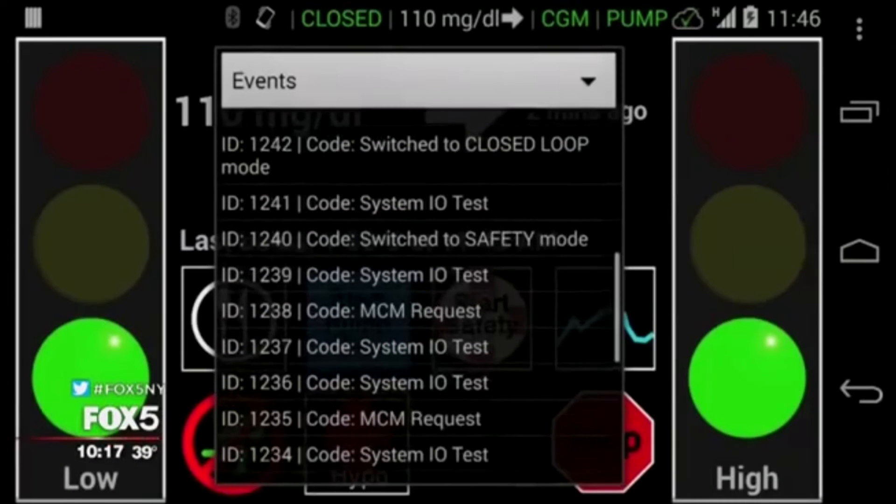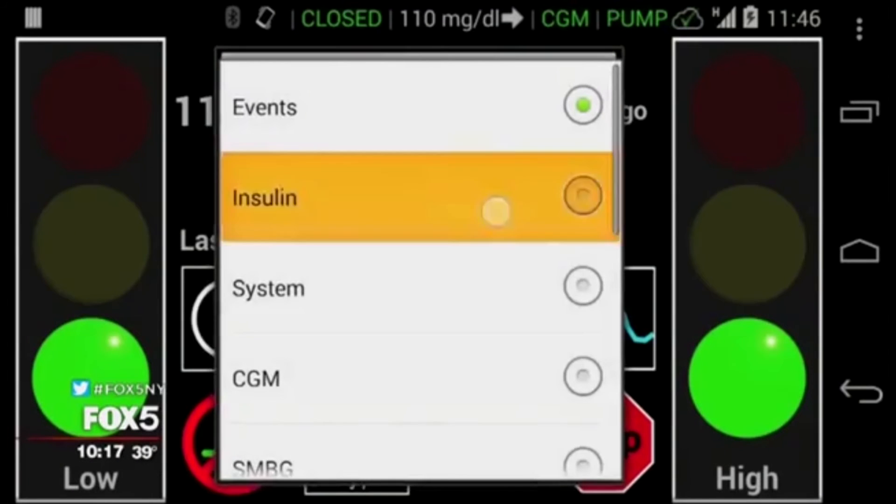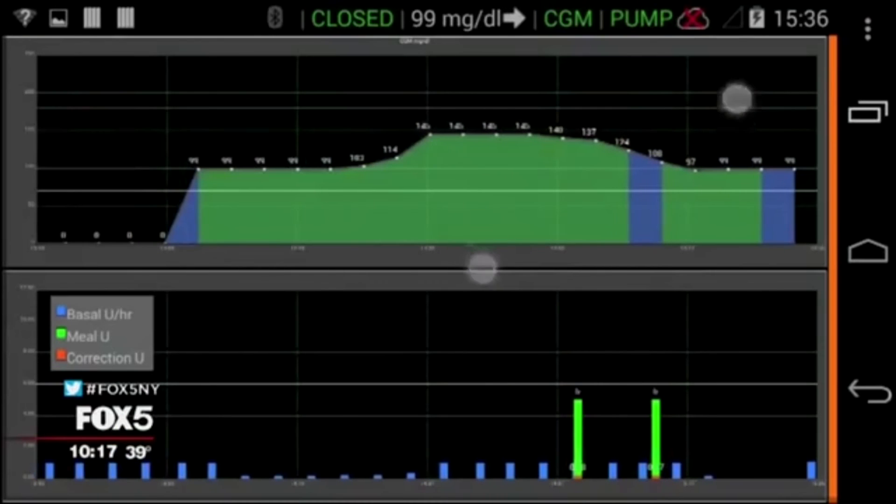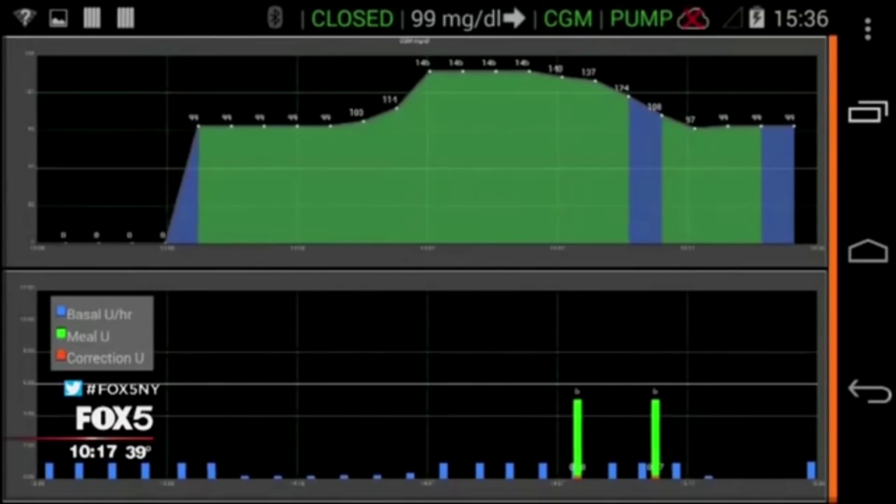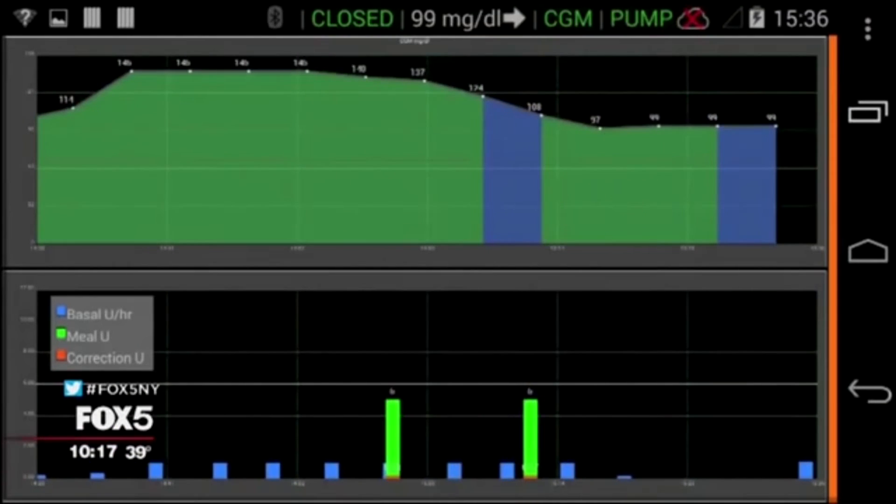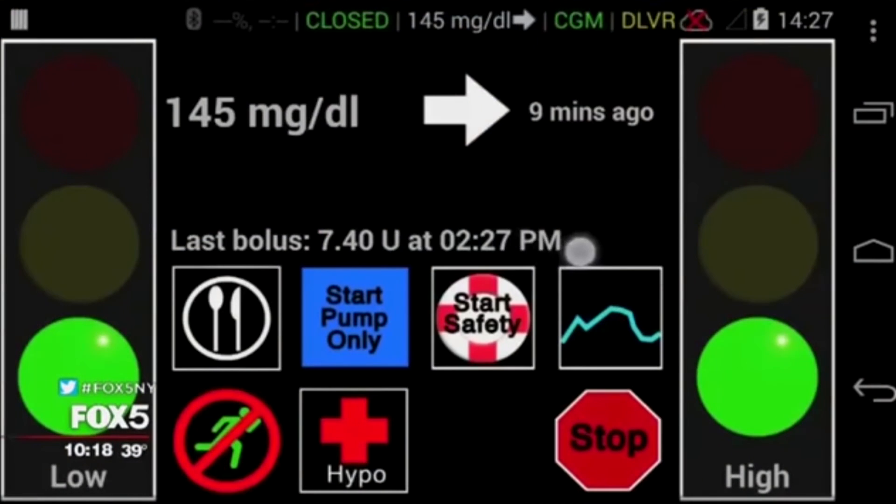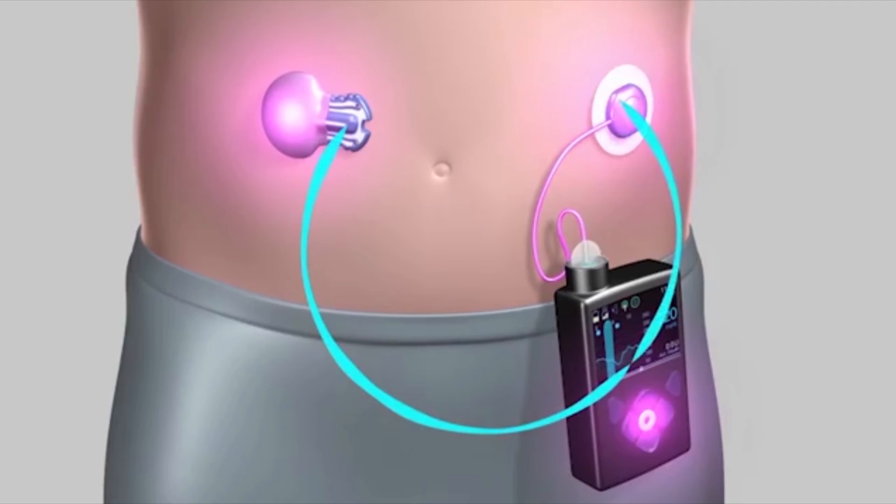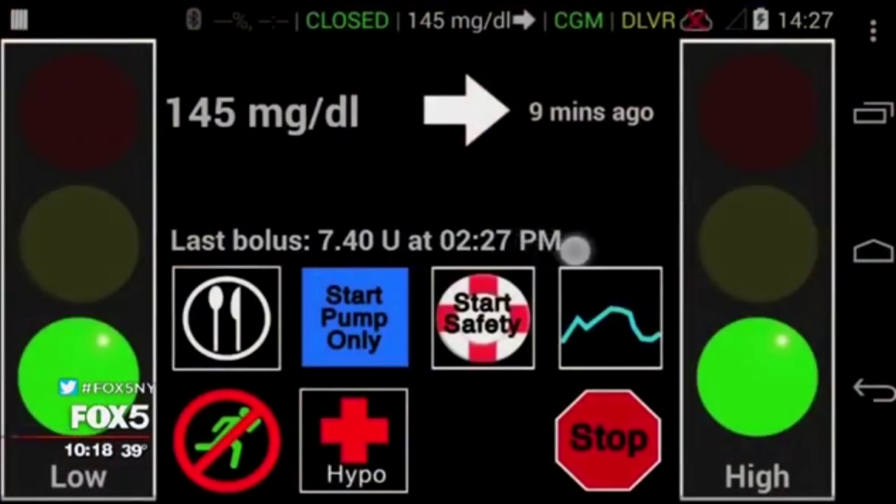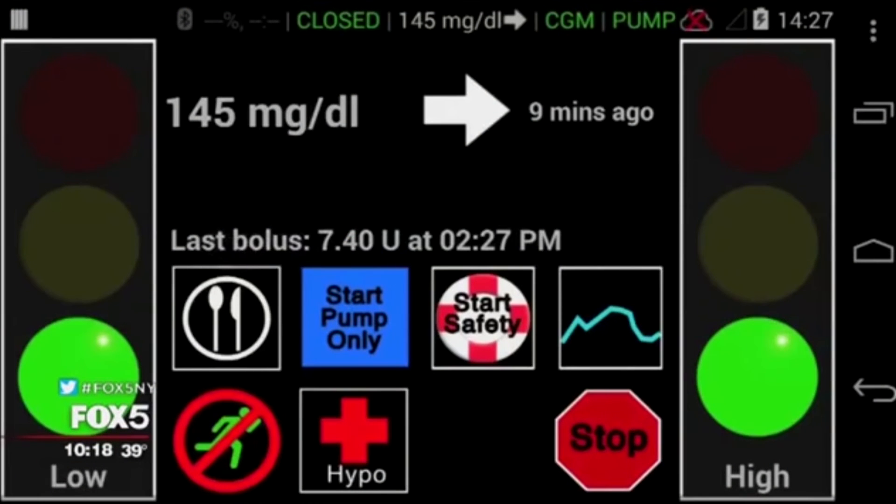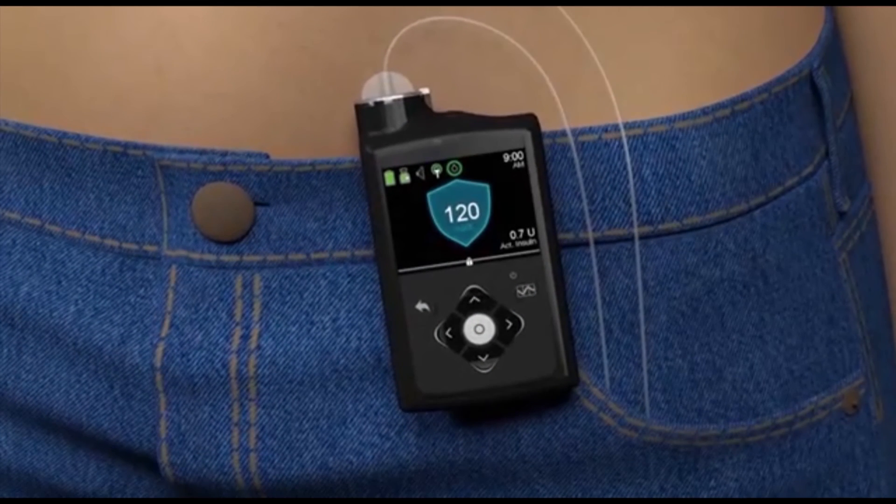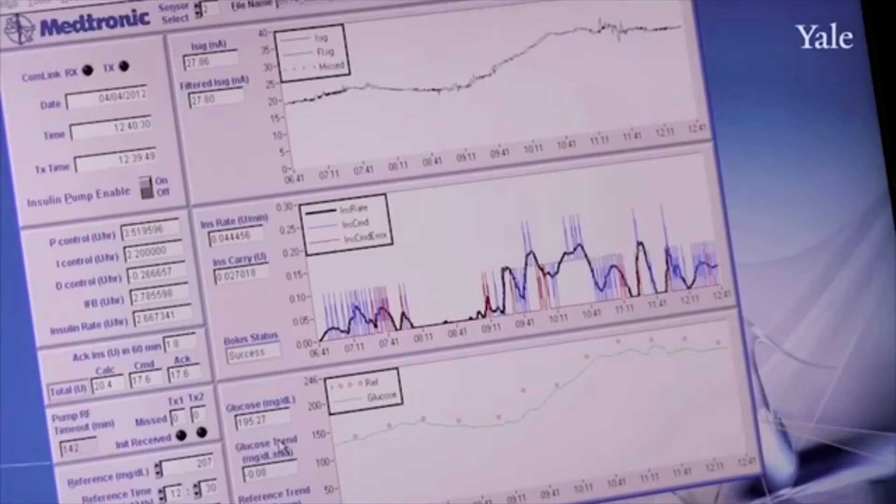A control algorithm is a software embedded in an external processor or controller that receives information from the CGM and performs a series of mathematical calculations. Based on these calculations, the controller sends dosing instructions to the infusion pump. The control algorithm can be run on any number of devices including an insulin pump, computer, smartphone or tablet.